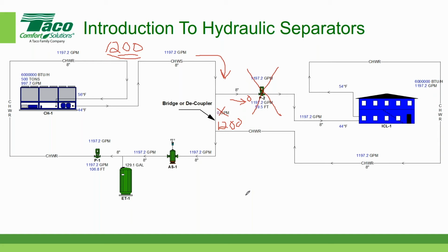A zero pressure bypass. What that means is that the water flowing in the primary loop has no influence on the flow of water in the secondary loop. So we're going back to 1,200 gallons per minute. What's flowing in this direction here is 1,200 gallons per minute. And this pipe is sized appropriately so that the pressure drop, I'll just put a little pressure gauge over here.